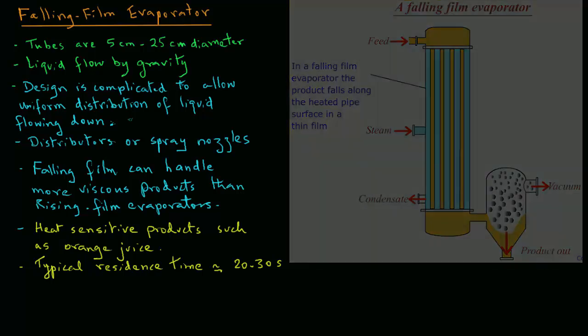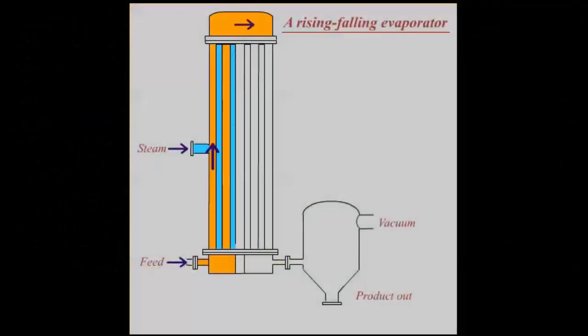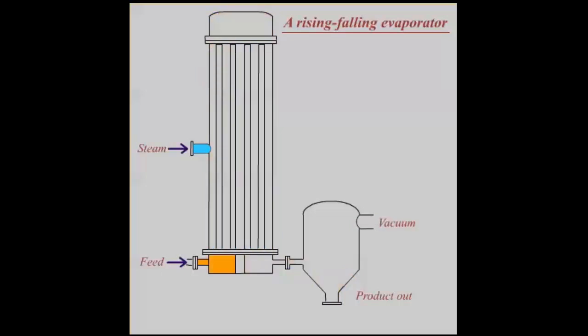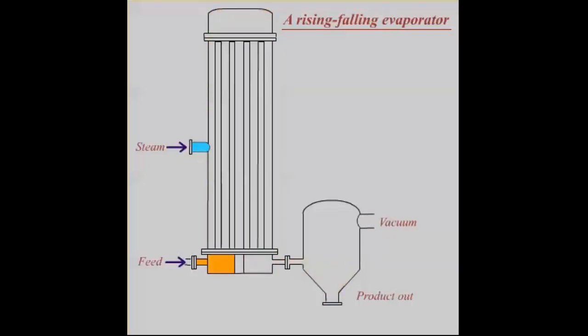There is another variation of an evaporator design that involves a rising film section in the beginning part of the evaporator and then a falling film section in the second part. The liquid feed first goes through the rising film section where the feed gets pre-concentrated and then it is allowed to fall by gravity in thin films in the falling film section.